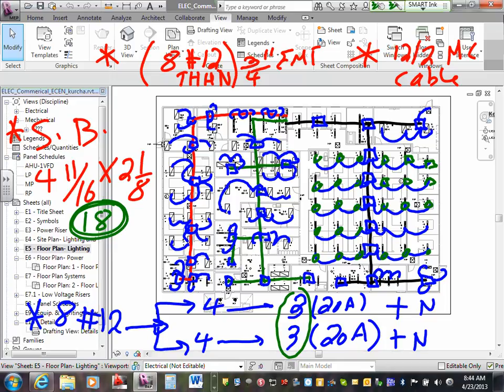Show me your conduit when you come. I'm not saying do it this way, Zach, but I need you to show me how you build your conduits. My conduit might be wrong, because Jeff might have picked up a circuit from here to here. Then in a case like this, guys, you take a conduit from this box to this system and you pull that conductor through them. Or they can meet right in the panel. Typically, I don't like to meet in the panel. I can pull these conduits, tie these two together so I can go from one conduit system to another too.